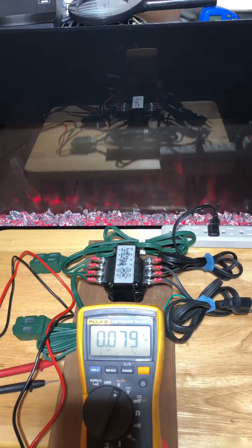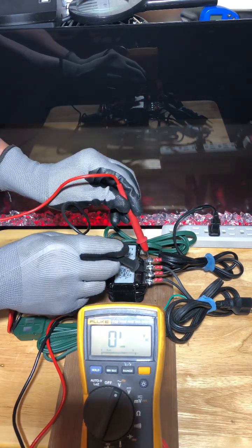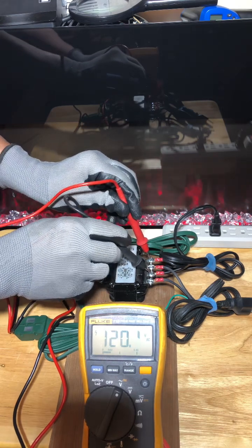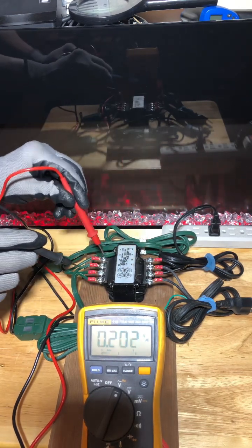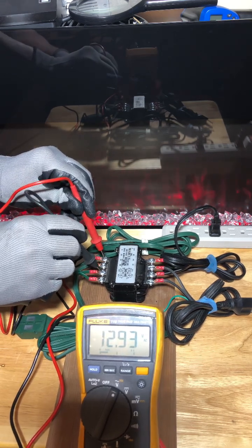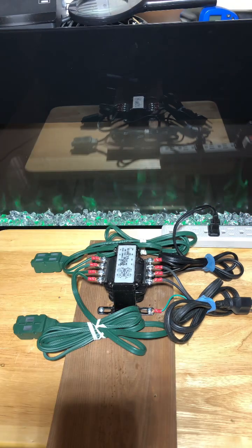Check the input and output power supply. There is 12.93 volts AC measured at the output. Therefore, we can use one transformer with two input power supplies of 120 volts and 240 volts, and two output power supplies of 12 volts AC and 24 volts AC.